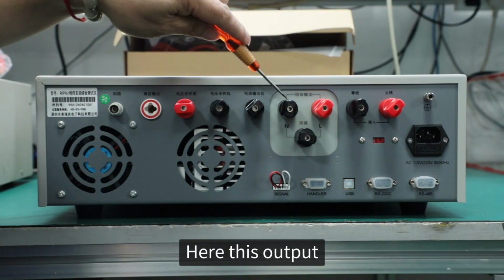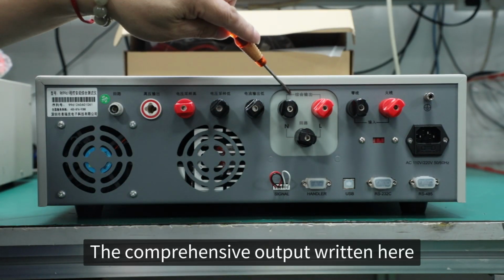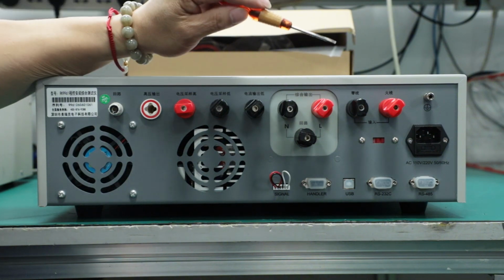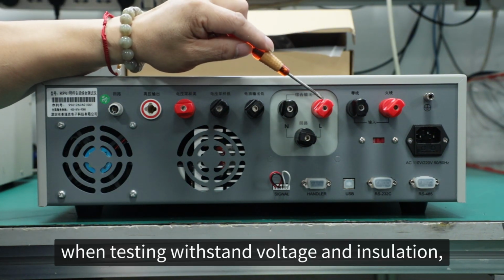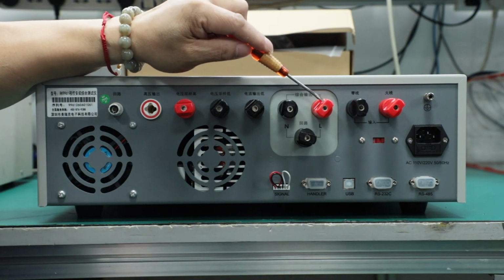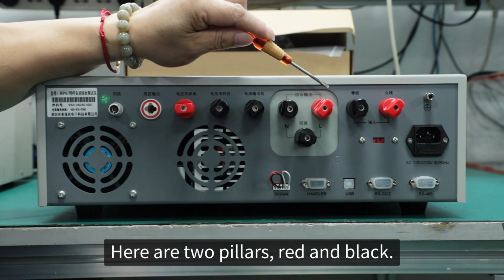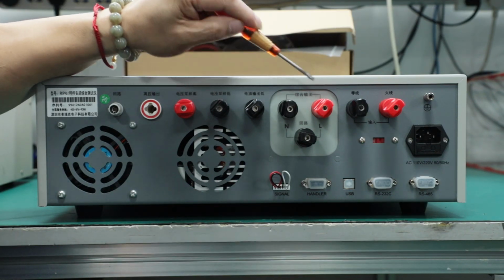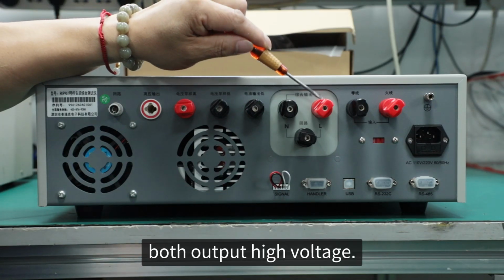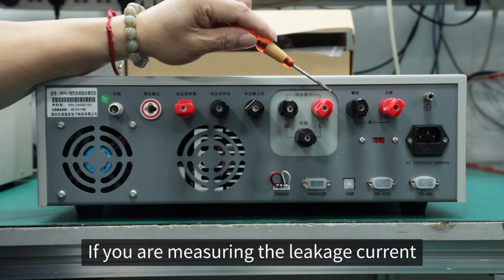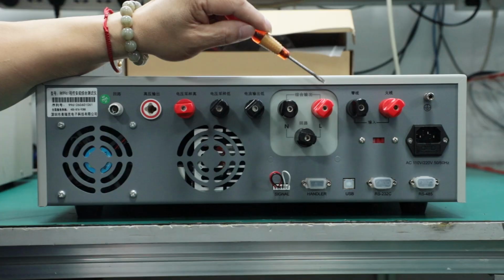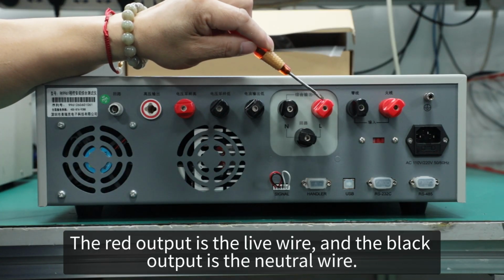Here this output, the comprehensive output written here. Comprehensive output is used when testing withstand voltage and insulation. Here are two pillars, red and black. They both output high voltage. If you are measuring the leakage current, the red output is the live wire, and the black output is the neutral wire.